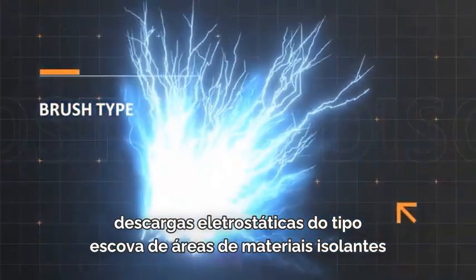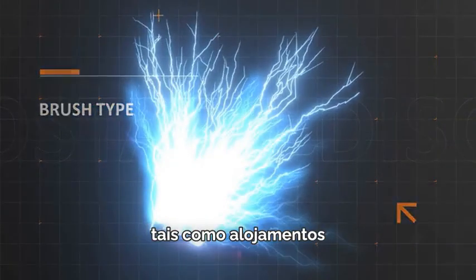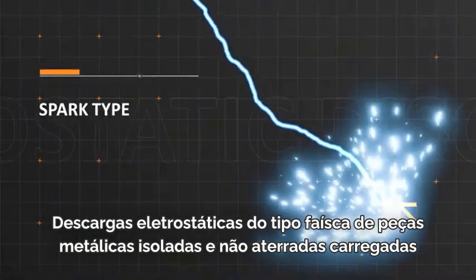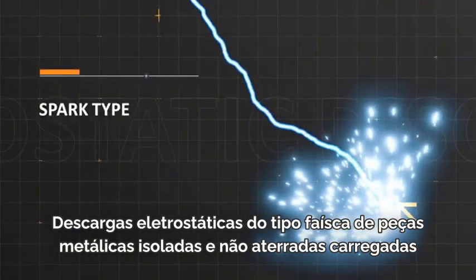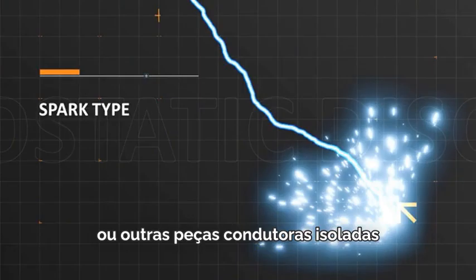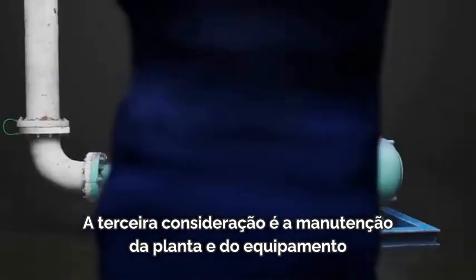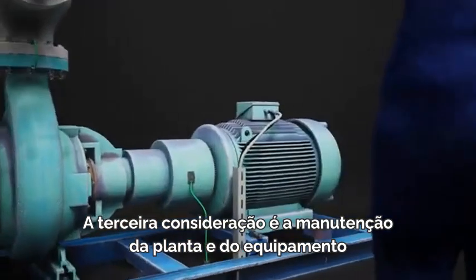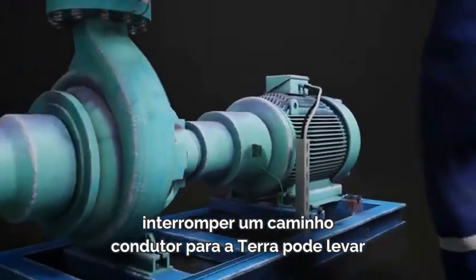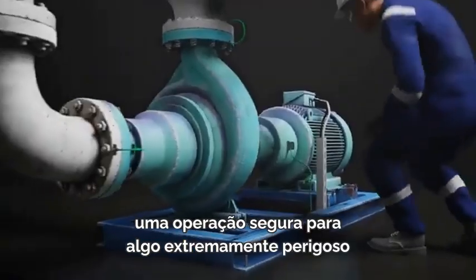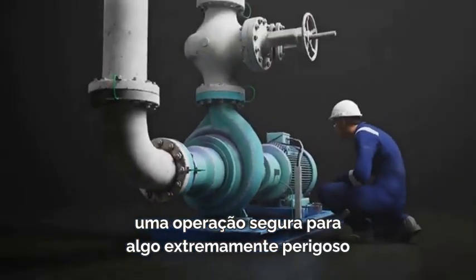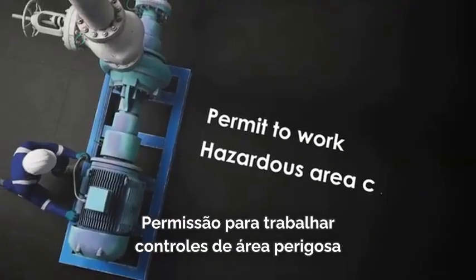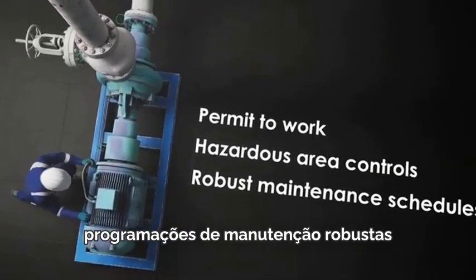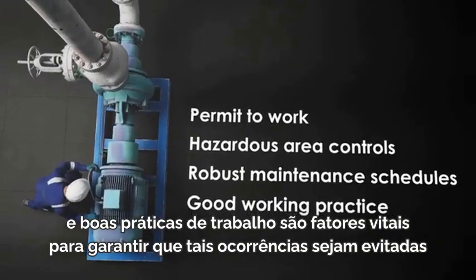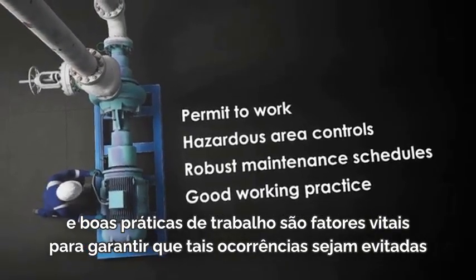For example, brush-type electrostatic discharges from areas of insulating materials such as housings. Spark-type electrostatic discharges from charged, isolated, unearthed metal parts or other isolated conducting parts. The third consideration is the maintenance of plant and equipment. For instance, interrupting a conductive path to Earth could take a safe operation to something extremely hazardous. Permit to work, hazardous area controls, robust maintenance schedules, and good working practice are all vital factors in ensuring such occurrences are avoided.